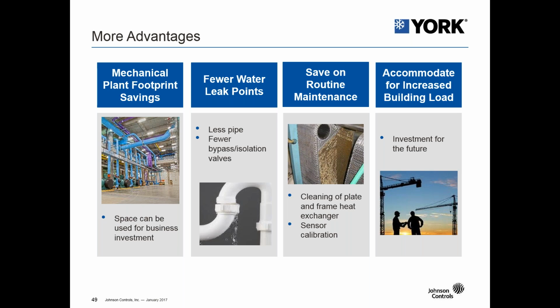So if we look at other advantages other than the first costs and the energy savings, more space can be used for whatever the client needs. So there's no mechanical footprint required because the water side economizer was removed. That allows for future expansion room if the building's going to grow, to add more chillers or larger chillers or other mechanical equipment in the space. There's fewer water leak points because there's less piping. There's no valves. There's no bypass or isolation valves that could leak over time. There's no routine maintenance required for cleaning the plate and frame heat exchanger, and it does give you the possibility of increasing the building load in the future if you have a tight mechanical space.